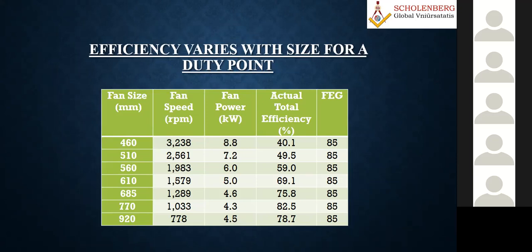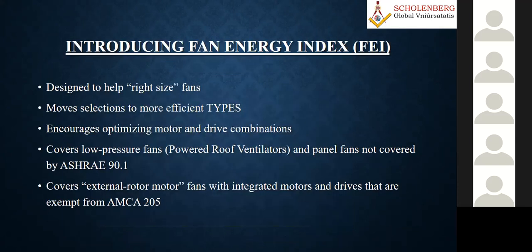Similarly, fan efficiency varies with size for a duty point across various diameters of the fan. I've been insisting every time that you should go for a factory inspection—before these fans are dispatched to site or used for assembling the air handling unit, you should do the performance test at the factory itself. That will definitely give you a clear idea of how much the efficiency changes as the fan size changes.